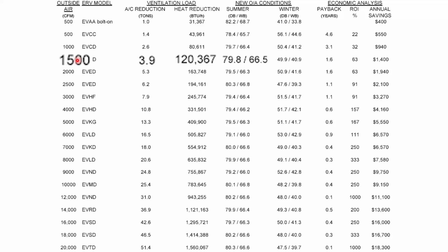In this example, it was a 95-degree day with, I believe, 74 wet bulb. Coming off the heat exchanger, I'm going to get 80 degrees and 67. 80, 67 is no coincidence. At our office, we specifically select ERVs targeting 80, 67. We could do ones that are worse, and we can do ones that are better, but the better ones cost more money, and the ones that do worse don't have a lot of benefit. So we target 80, 67 as kind of a cheat because 80, 67 is the same inlet conditions that all your evaporator coils are rated at. So we figure if we can get to 80, 67 with the ERV, it's like your evaporator doesn't even have any outside air anyway. So it's kind of a nice spot.